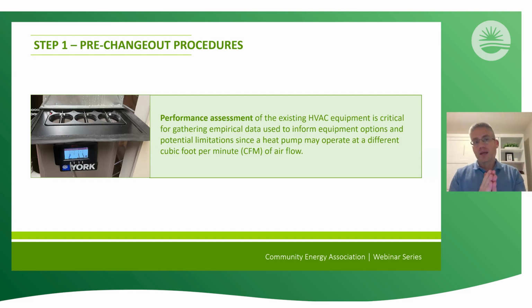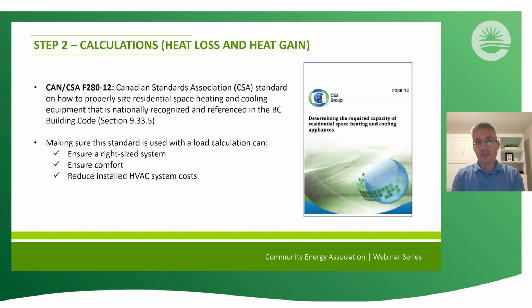And again, that's about doing actual testing, like static pressure testing or airflow testing, in the case of having a flow grid like we do in this picture. That can really inform your decision making about whether you need ducting enhancements or whether you have any limitations with the actual heat pump that you can size for your house. But again, it's not a visual piece, it's actual collecting of data to make that informed decision. So those three pieces are really the critical parts of proper pre-change out that homeowners should be expecting, or at least asking their contractor to participate in as they're doing this.